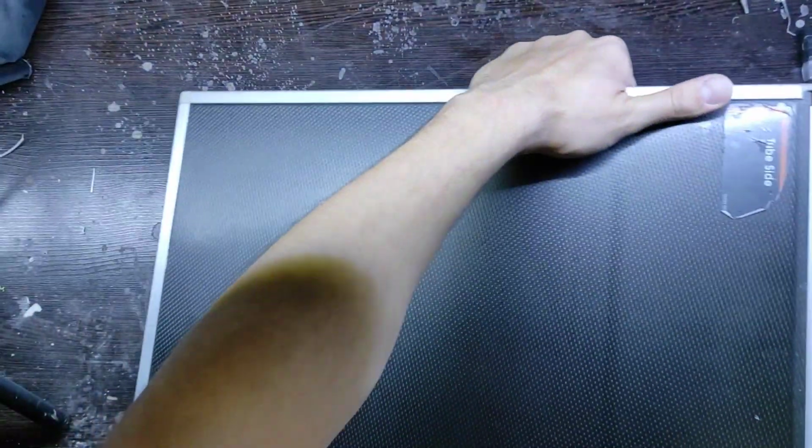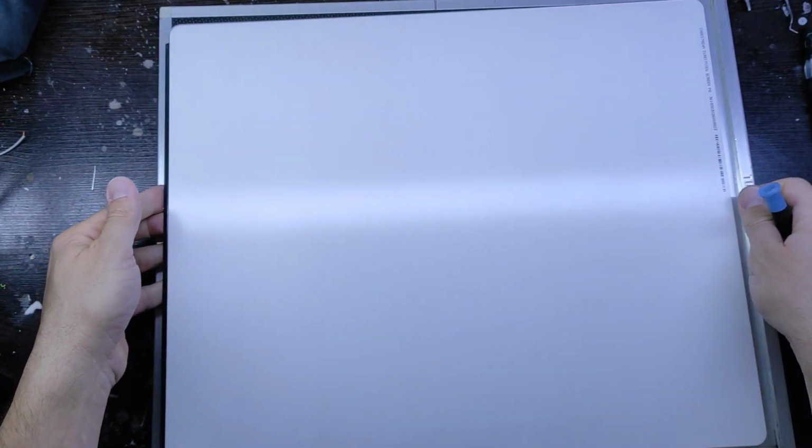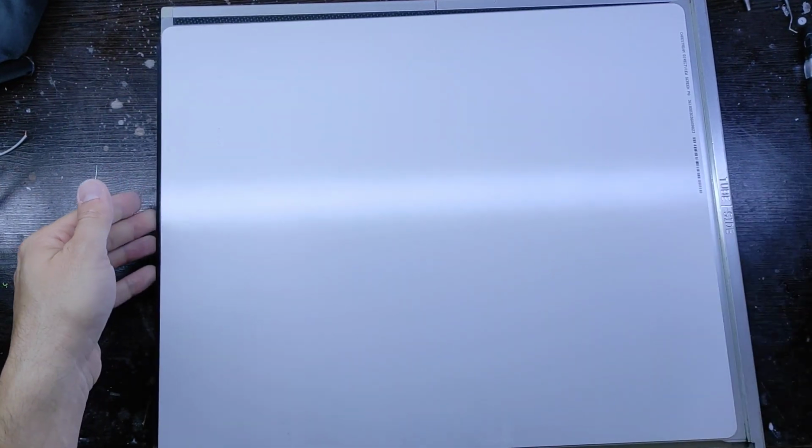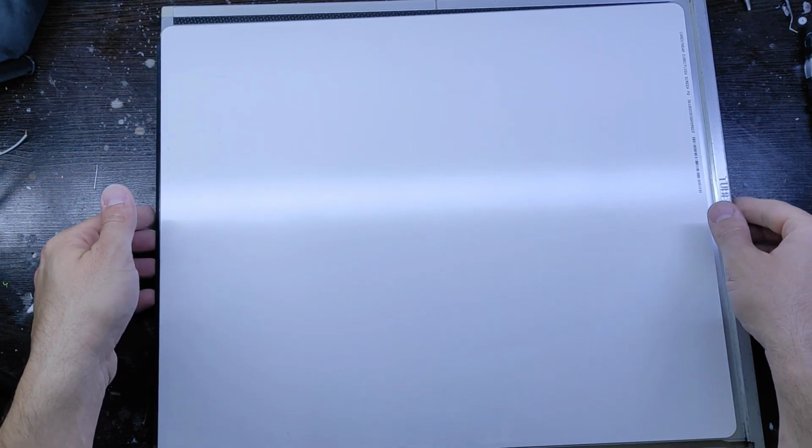This part that I'm opening is the main part of the cassette of the CR system, which consists of chemical materials.